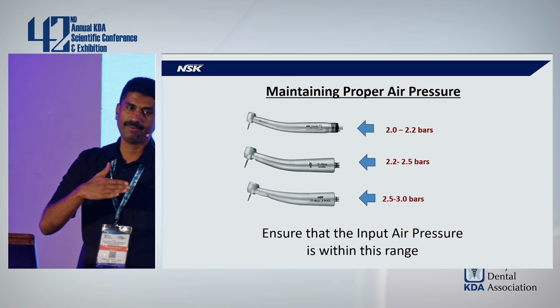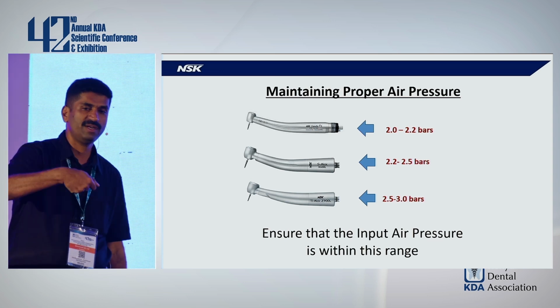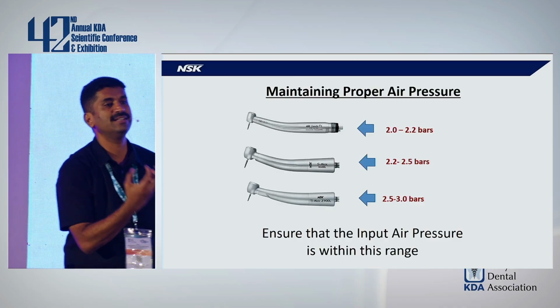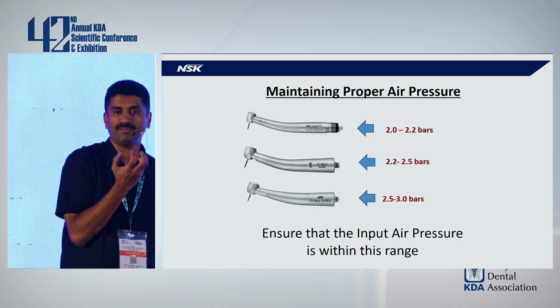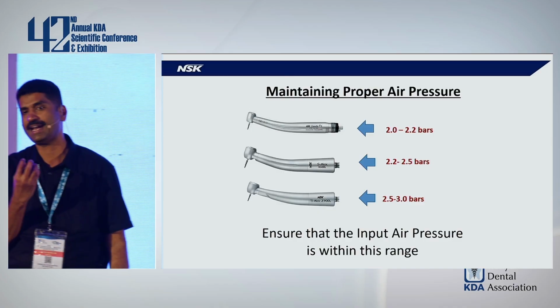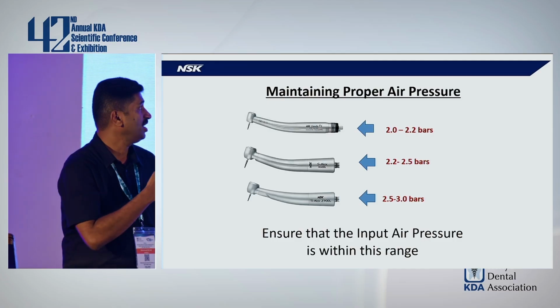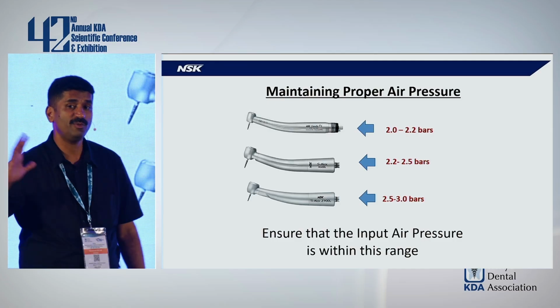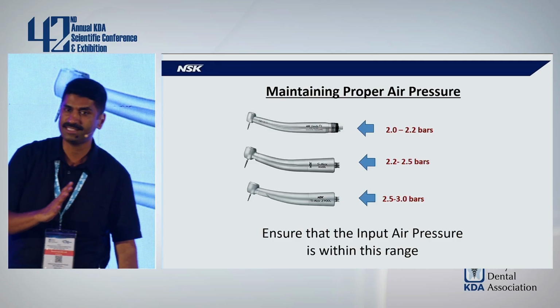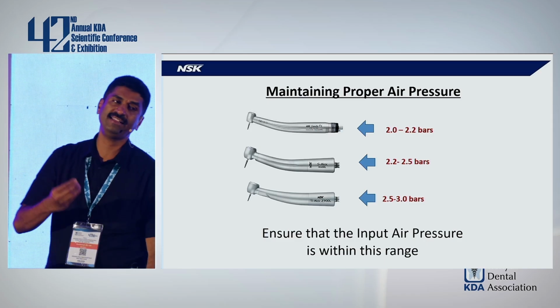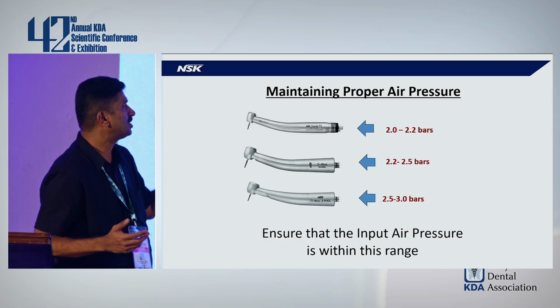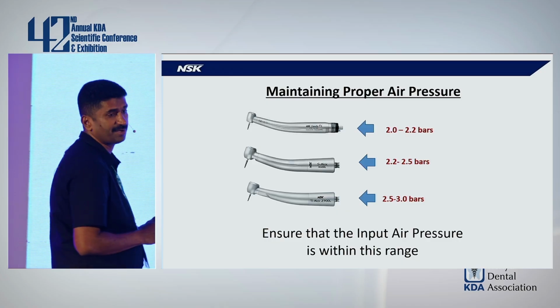If it's low air pressure, you will not know. You will tend to apply load. It will cause the reverse effect on the ball bearings and the cartridge of the handpiece will get damaged. If you're running at a very high pressure, there will be excessive load falling on the handpiece, because of which, again, the cartridges may get damaged. So it's very important to maintain this air pressure.